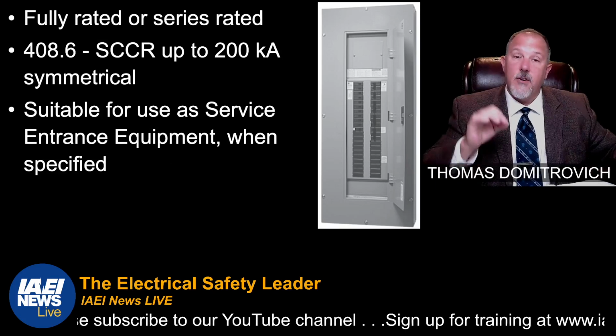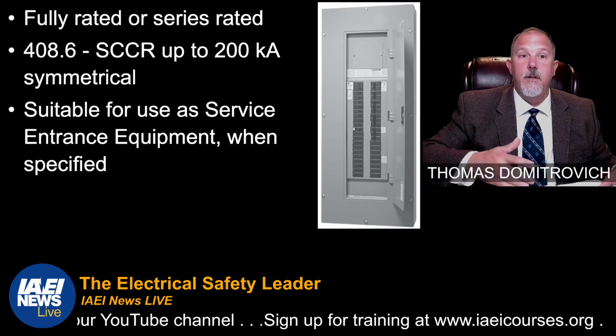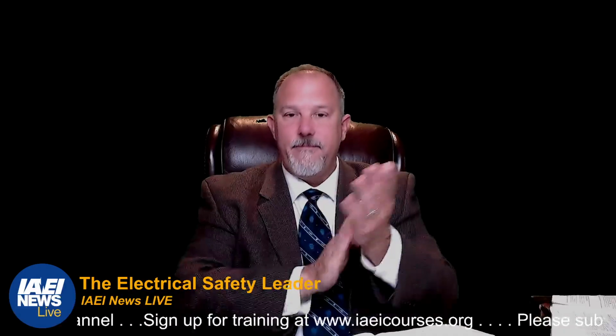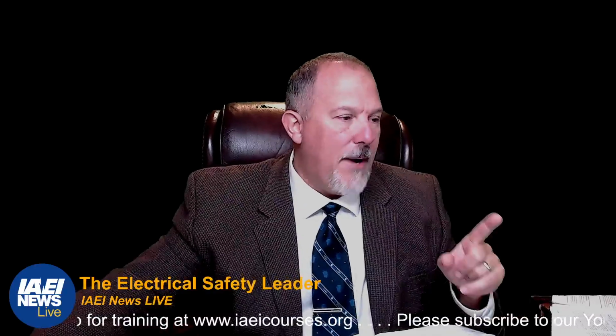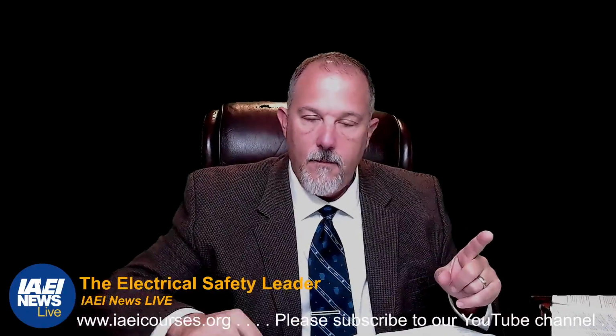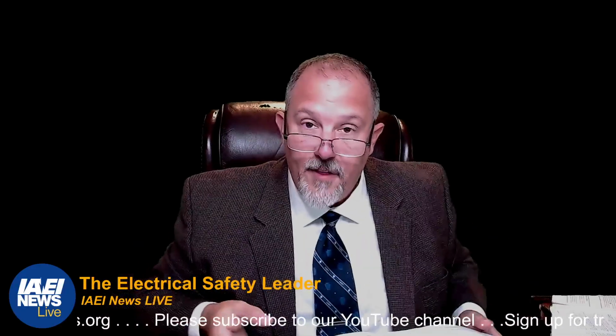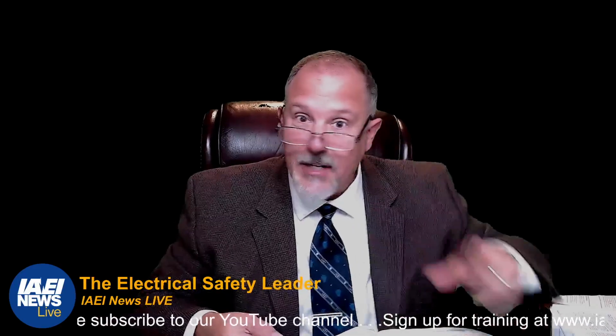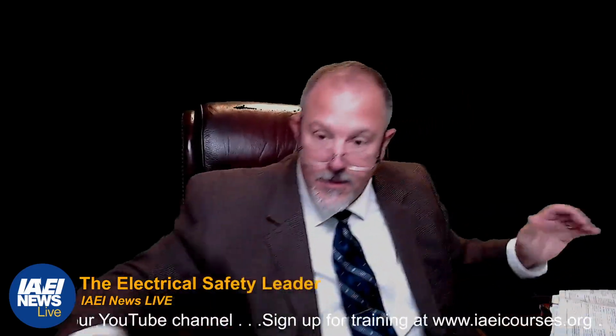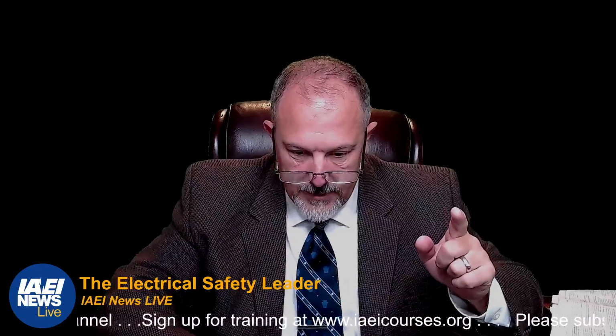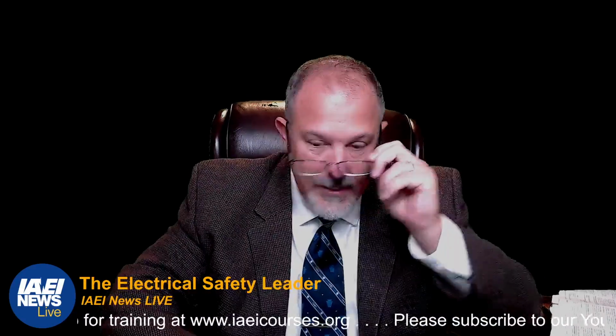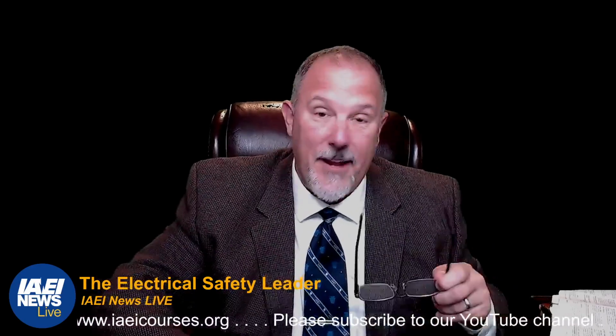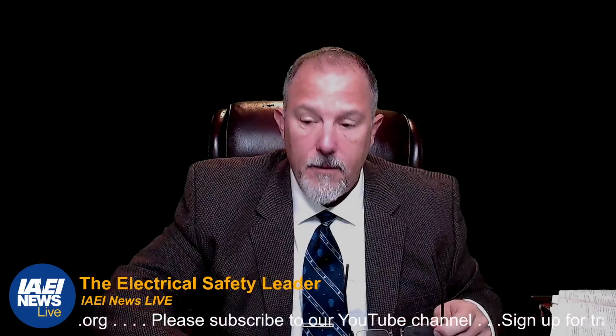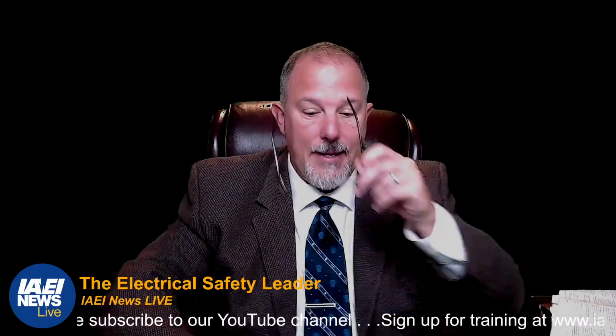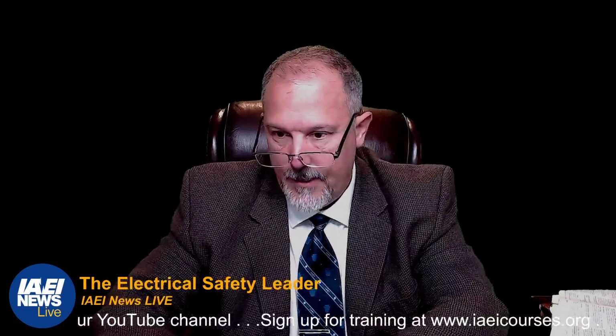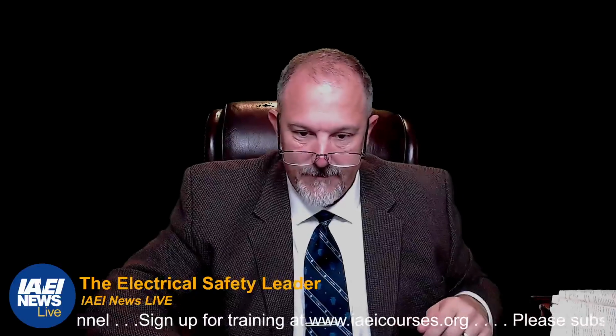Now, the way they determine it, a panel board is not marked by the manufacturer. Oh, this is a good one. A panel board is not marked by the manufacturer with a short circuit current rating. Now, oh boy, I'm watching. I can see you cringing right now. I can just hear the gnashing of teeth and people saying, what did he just say? Because I make panel boards, and I've had this discussion, and I mark the short circuit current rating on my equipment. Let me tell you why I say that. Because it's true.